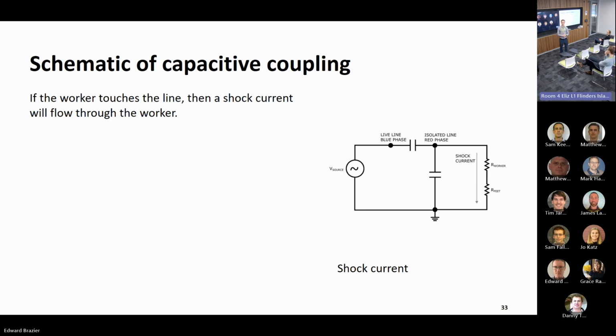If you have a very long line, the capacitance will be high, and the reactance of those capacitors will be lower, so you'll get a higher charging current, which will flow through the worker if they touch it after removing the earths. And again, that doesn't depend on how long ago you removed the earths - that hazard will appear immediately.